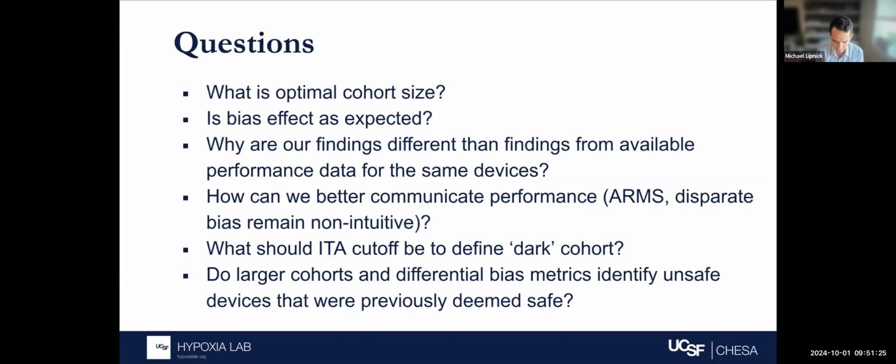The experience that I can refer to is that we pull percent modulation off of our PM1000N, and we pull perfusion index off of our RAD97 from Masimo. We found a correction factor that makes them seem very similar, but we've been told by the companies that they are in fact not the same, but we don't have access to those formulas. So I don't know if that answers your question, but I would sum it up as it's not necessarily apples to apples, and it's not necessarily raw percent modulation depending on what device you have, based on the information that I have available to me.